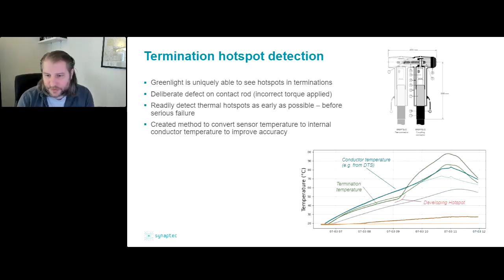Even temperature probes, like conventional sensors embedded in the conductor, couldn't see this, because they're just a little too far away from the termination and didn't see the hotspot develop. The same goes for DTS fiber, which would similarly be too far away from the termination to spot this. There's also the spatial resolution factor for DTS systems that means it's not great at finding point temperatures, because it's averaging things out.